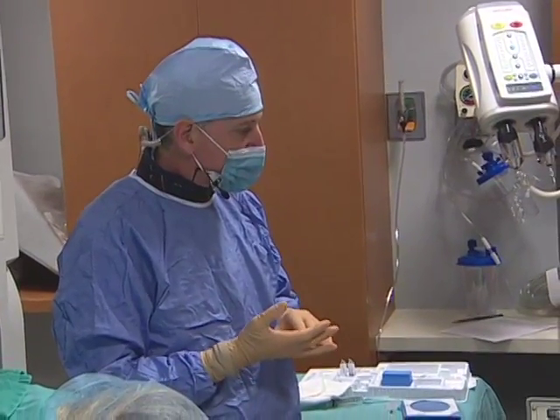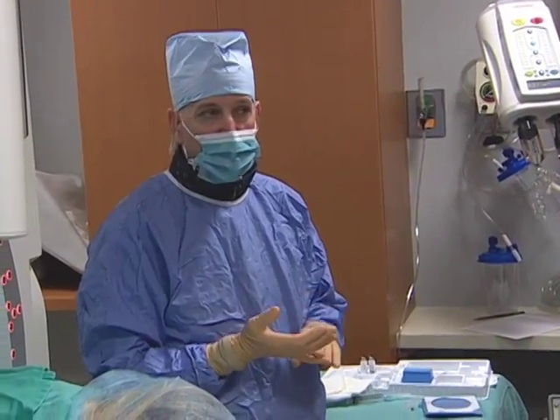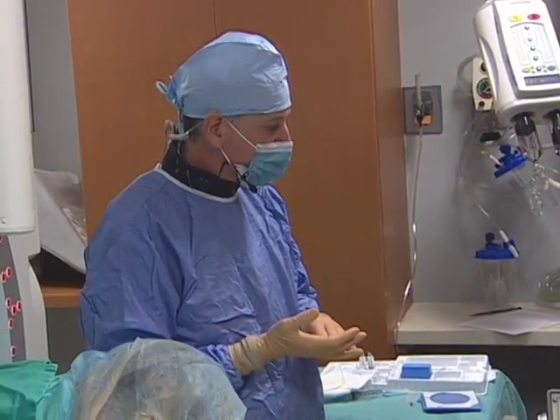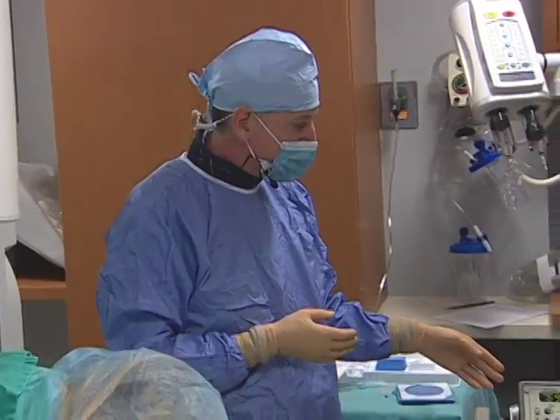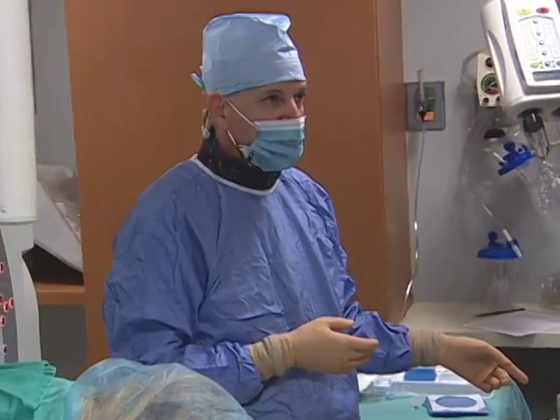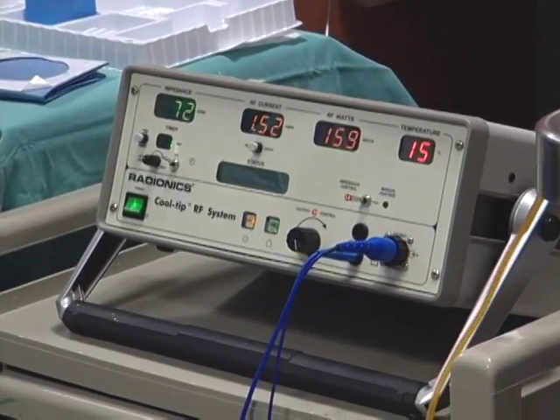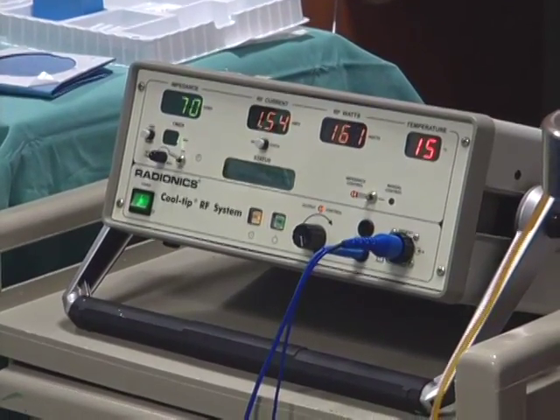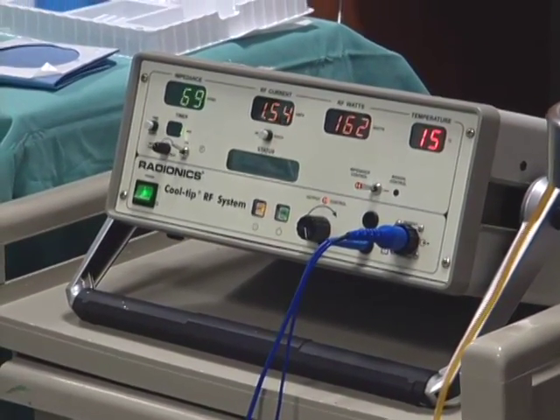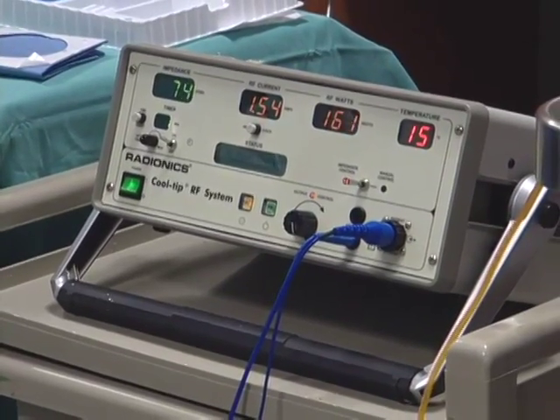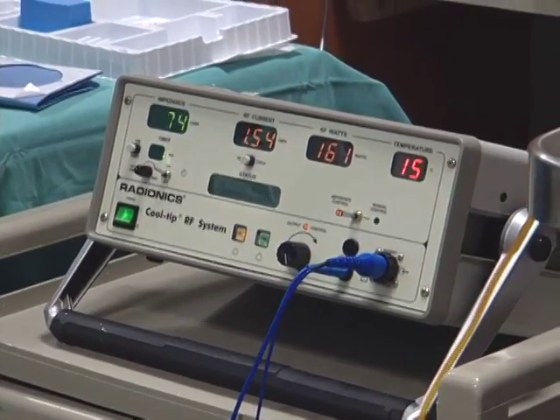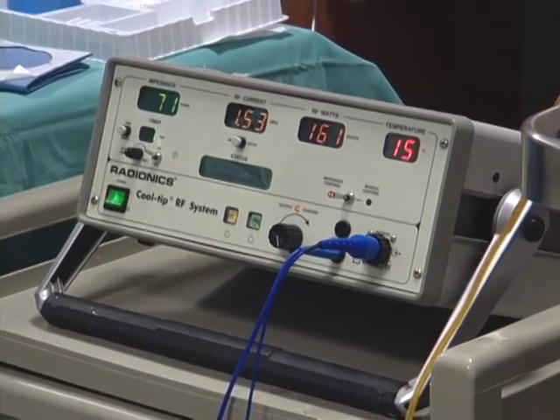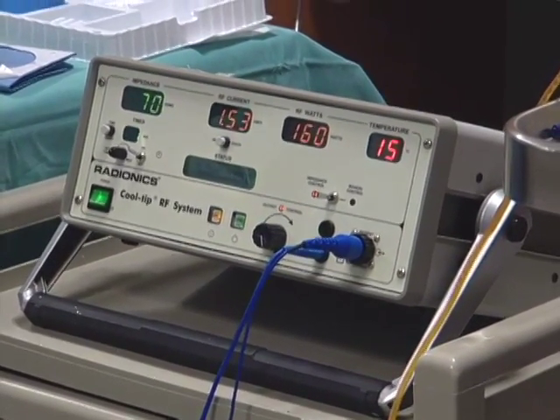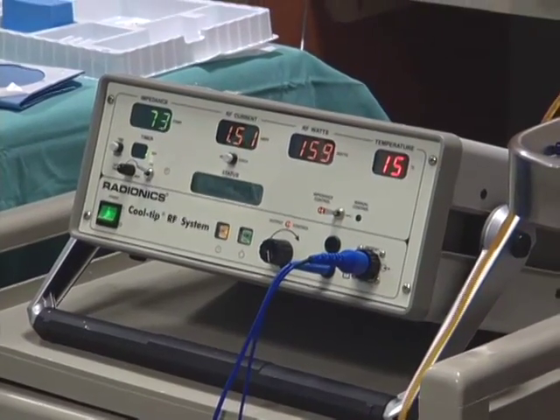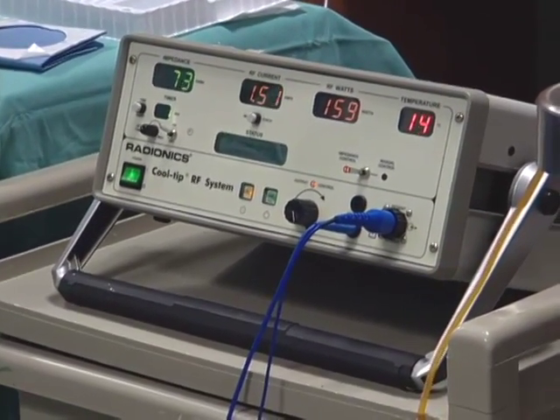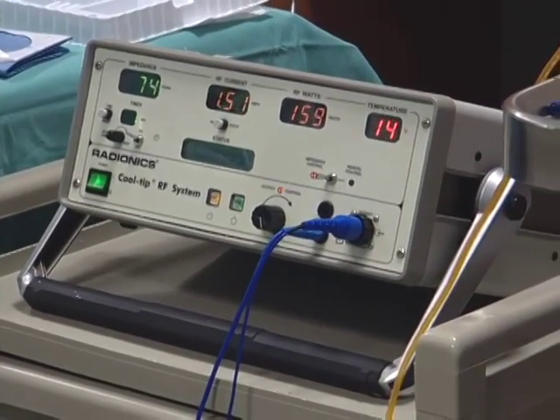In order to counteract that high concentration of energy, they use 2 techniques: the cooling of the probe and the pulsation of energy. Basically, the box monitors the impedance of the tissue around the probe tip. If that impedance rises rapidly, that indicates boiling and charring and overheating in that area, which will inhibit further ablation. So the device then goes off for about 20 seconds, lets the area cool off, and then powers up again to continue ablation. And we set for a maximum of 8 minutes for these small kidney tumors. We may shorten that if we start getting high impedance levels.